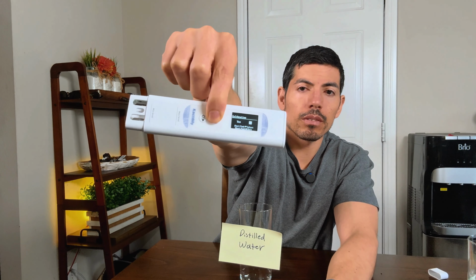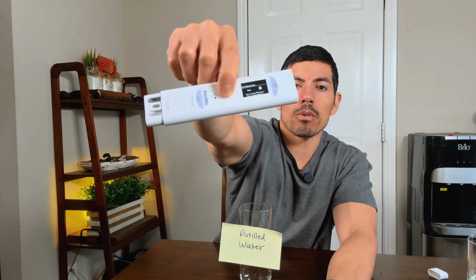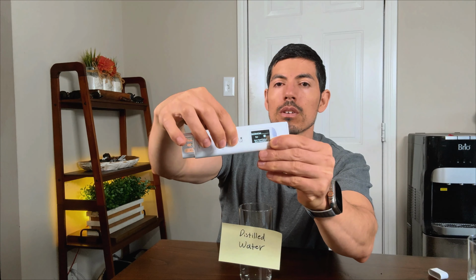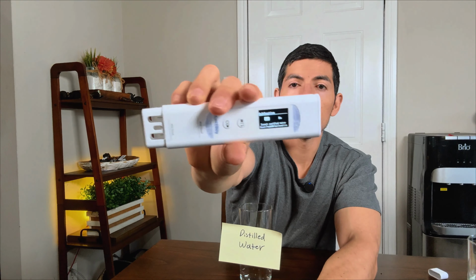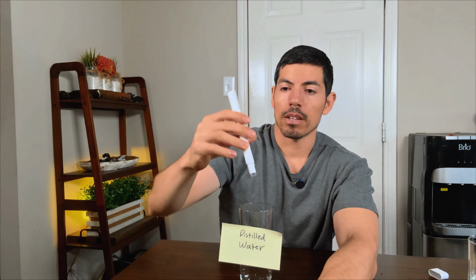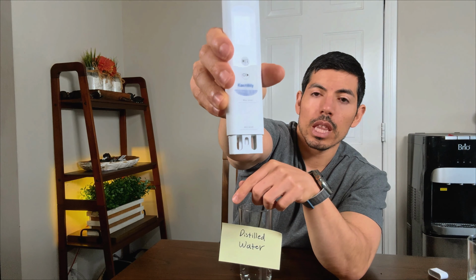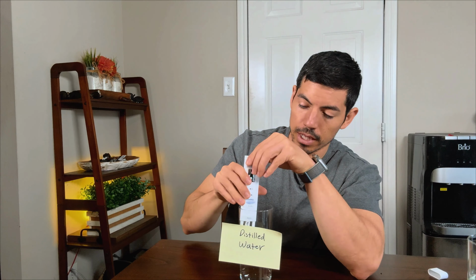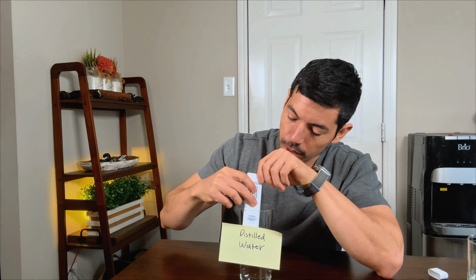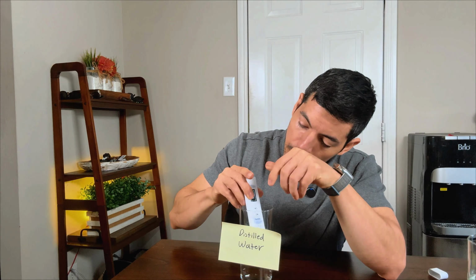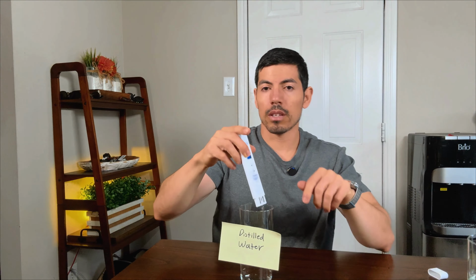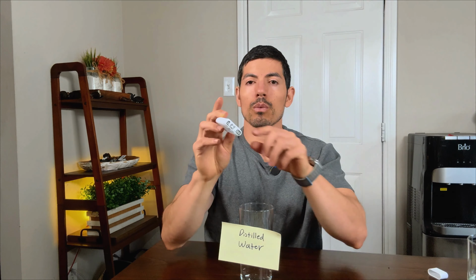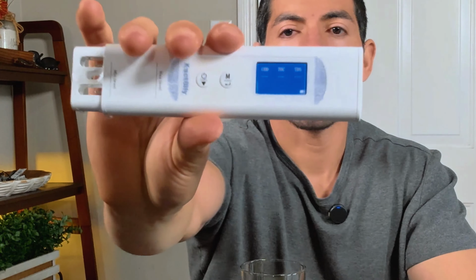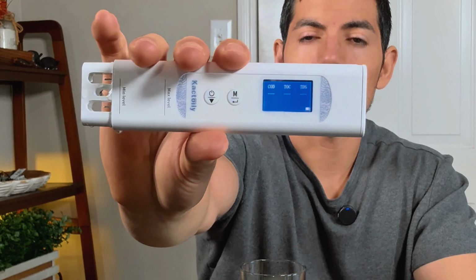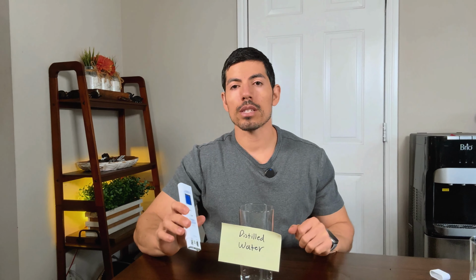And then we'll get the calibration option. And then we'll go ahead and press the M button once more. Okay, and then we'll press the power button to go to calibration. And then it'll say insert purified water, short press M calibration. So we'll put it in the water and then press the M button again. And we have our min and max levels that we want to put the probe into. So go ahead and put it in. We'll go ahead and press once. And it says calibration successful. So it really quickly went on the screen. It said calibration successful, and this is the screen that you'll come to when the calibration is finished and successful. So now we're ready to start testing other water here.